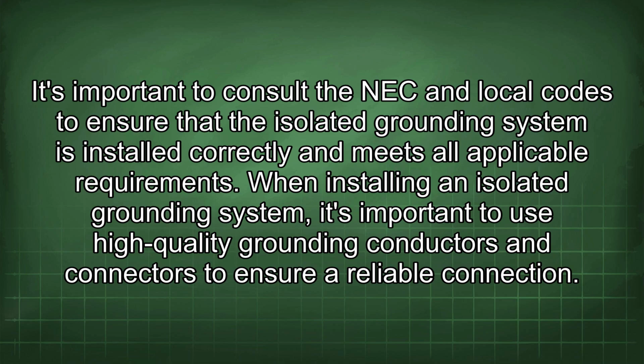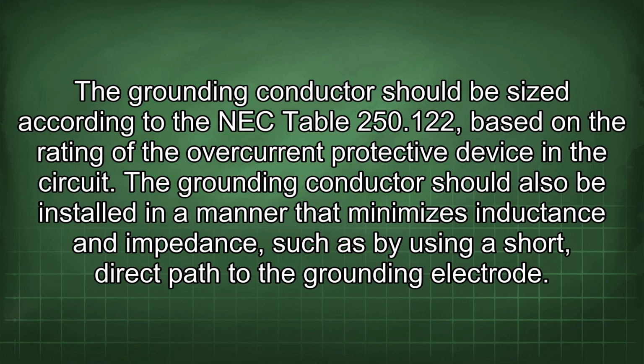When installing an isolated grounding system, it's important to use high-quality grounding conductors and connectors to ensure a reliable connection. The grounding conductor should be sized according to NEC Table 250.122, based on the rating of the overcurrent protective device in the circuit. The grounding conductor should also be installed in a manner that minimizes inductance and impedance, such as by using a short, direct path to the grounding electrode.